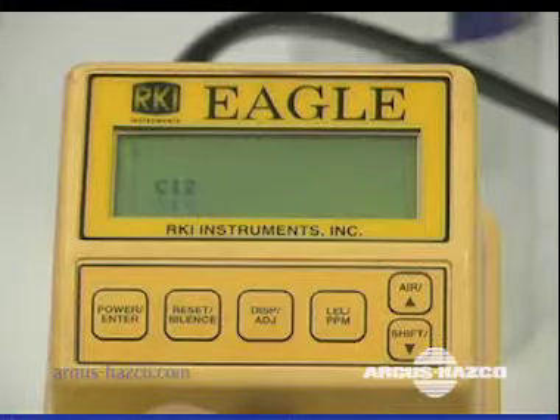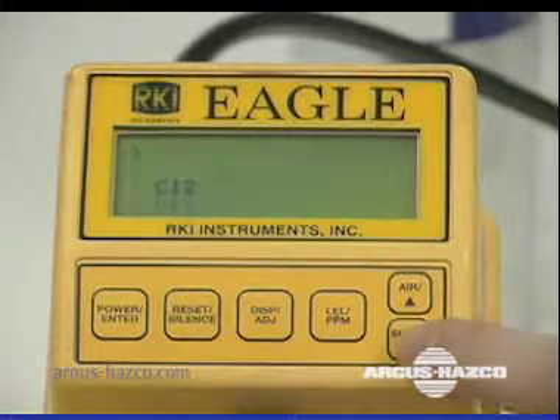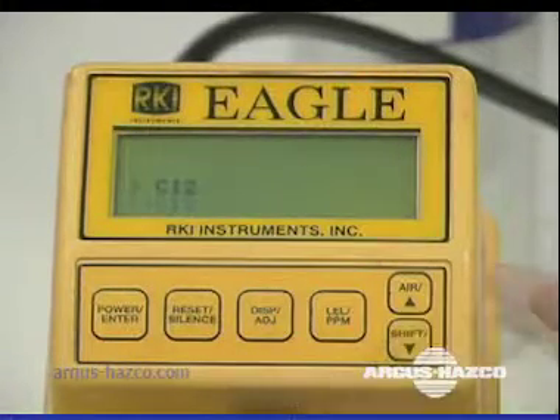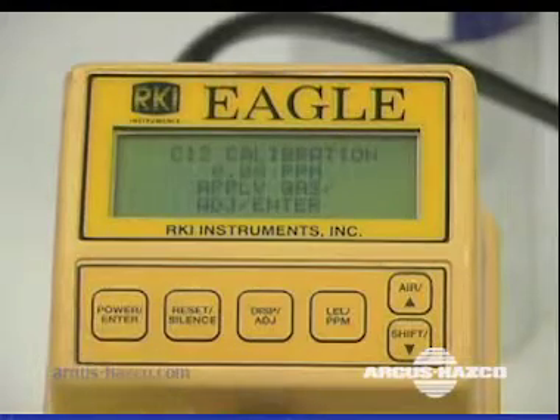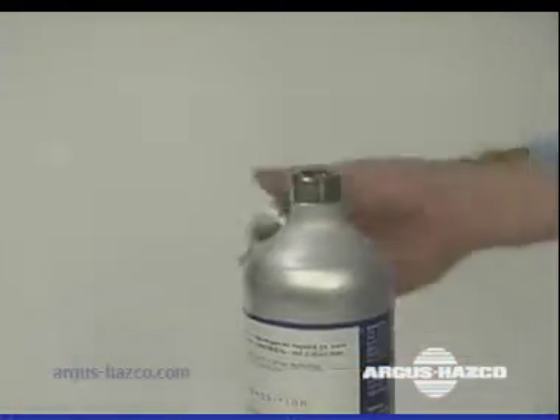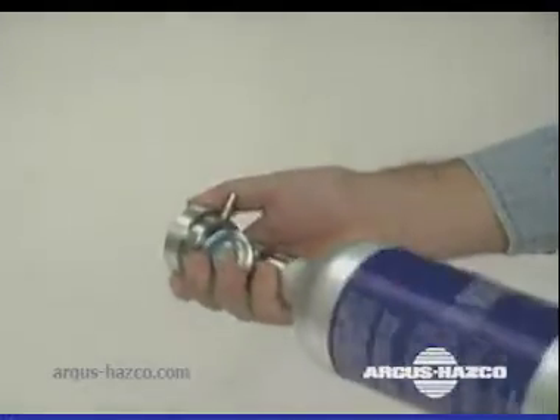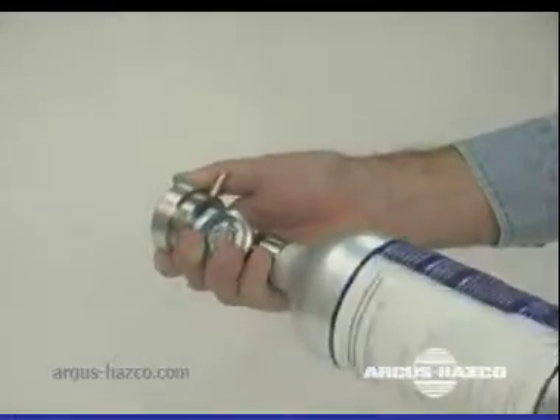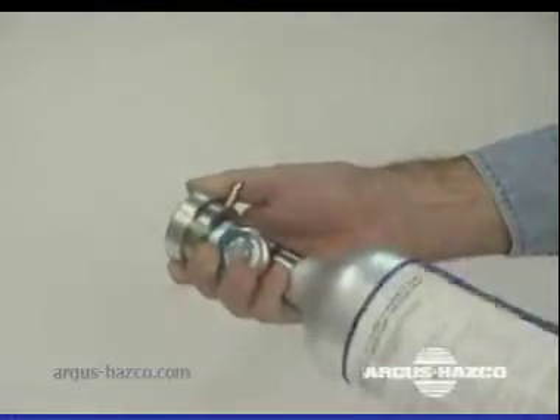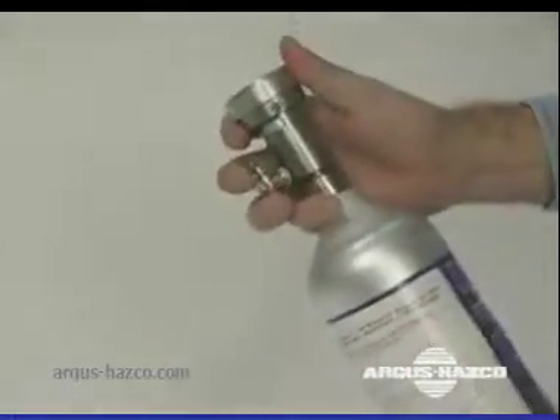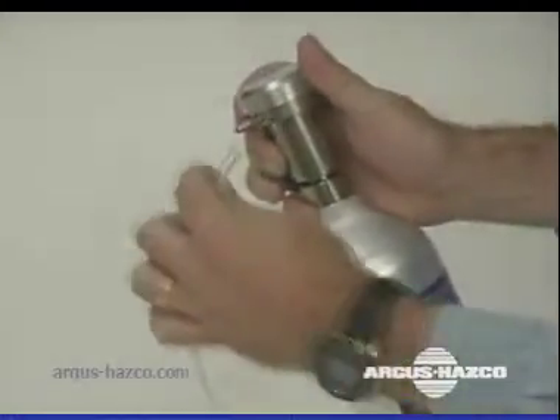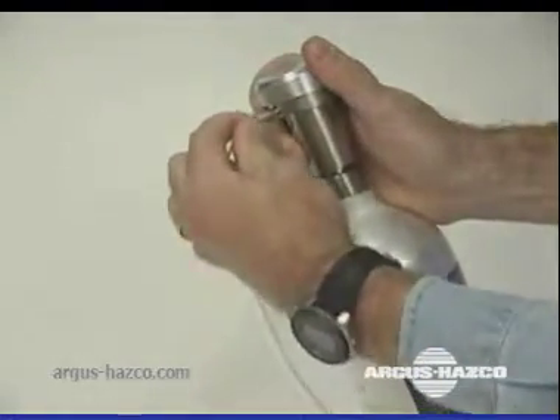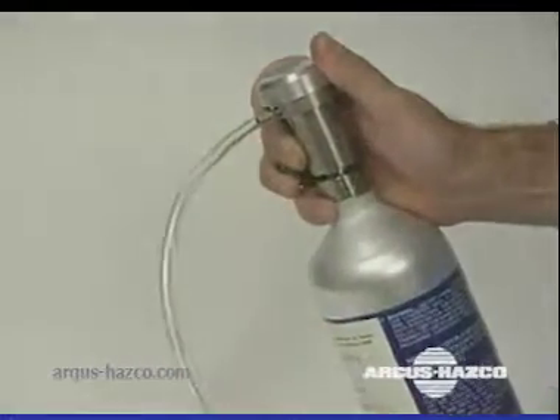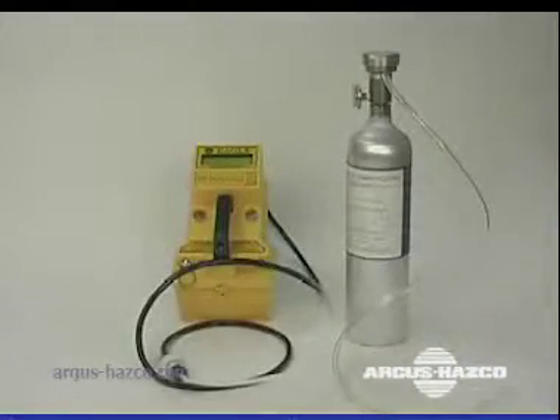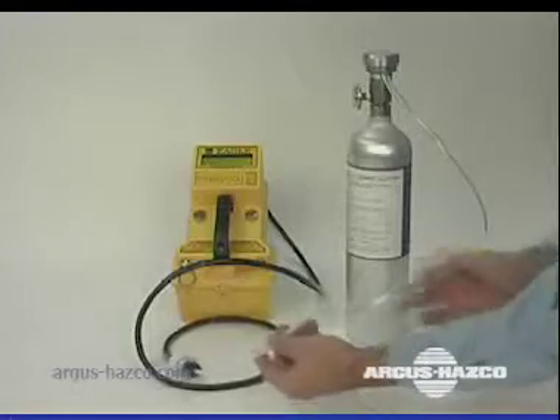At the single calibration screen, scroll down to the appropriate gas, then press the Enter button. Screw the calibration cylinder to the regulator. Next, connect the tubing to the regulator. Now connect the tubing from the regulator to the Eagle probe.